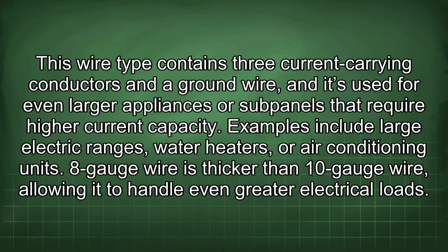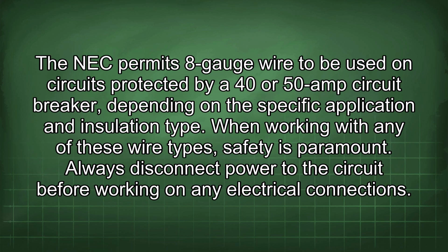8-gauge wire is thicker than 10-gauge wire, allowing it to handle even greater electrical loads. The NEC permits 8-gauge wire to be used on circuits protected by a 40 or 50 amp circuit breaker, depending on the specific application and insulation type.